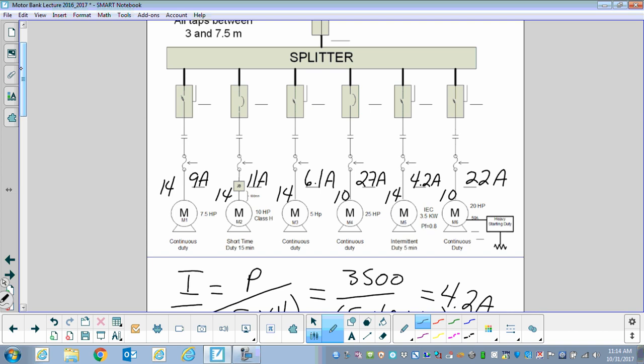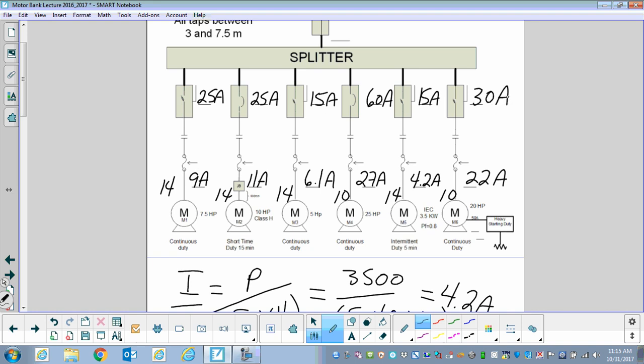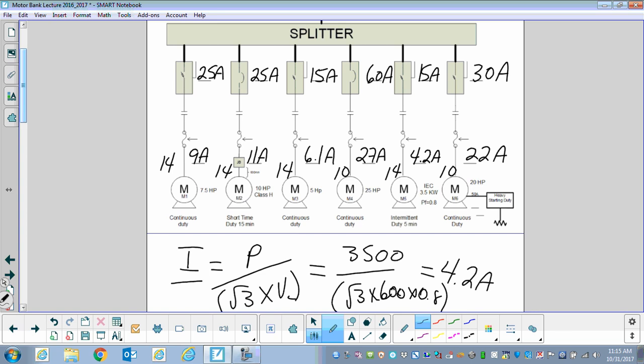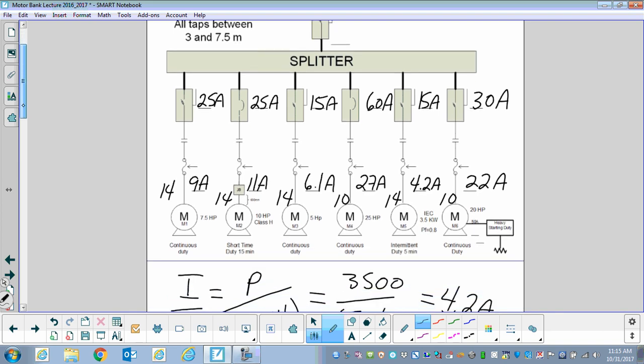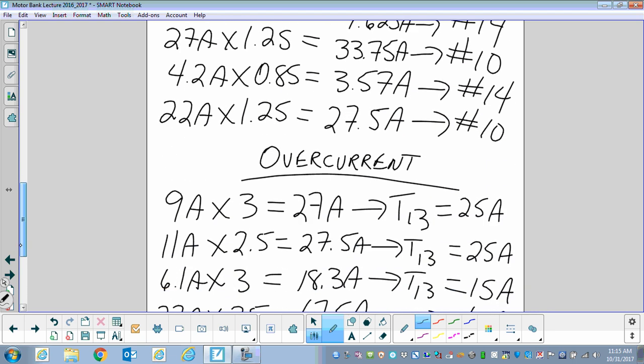Let's put these in: 25-amp, 25-amp, 15-amp, 60-amp, 15-amp, and 30-amp. That covers the individual branch circuit overcurrent devices. You'll notice we have two breakers and the rest are fuses, and the main overcurrent device is a fuse. We're going to have to revisit those breakers and calculate them as fuses when we determine the main overcurrent device.